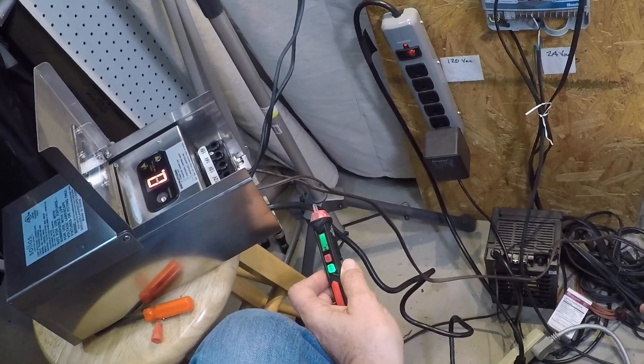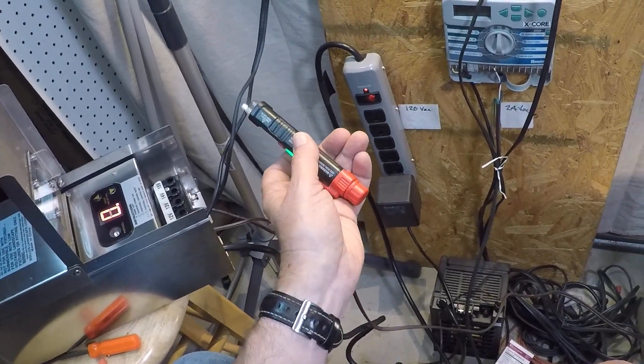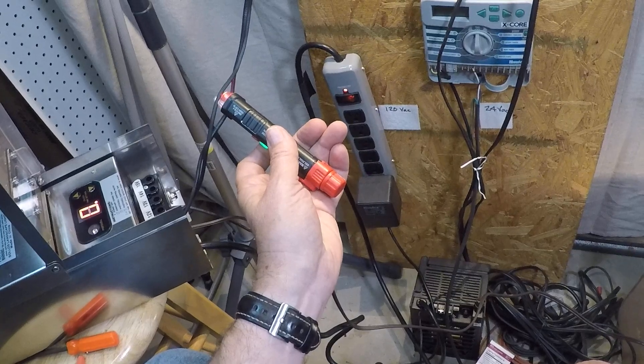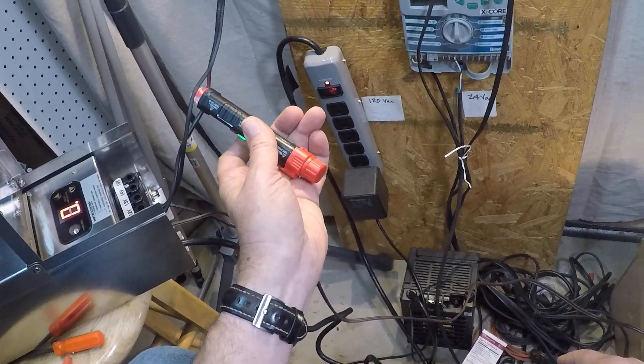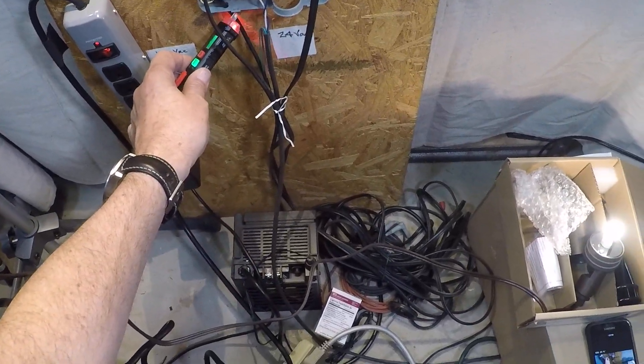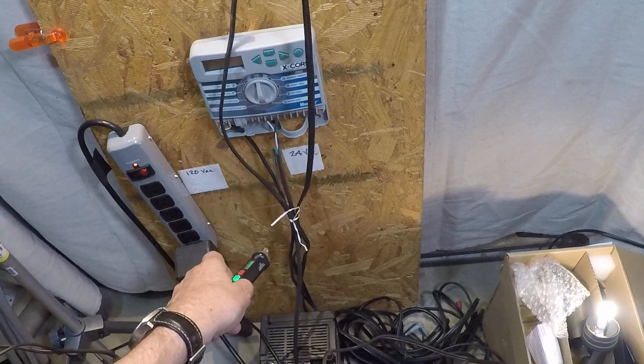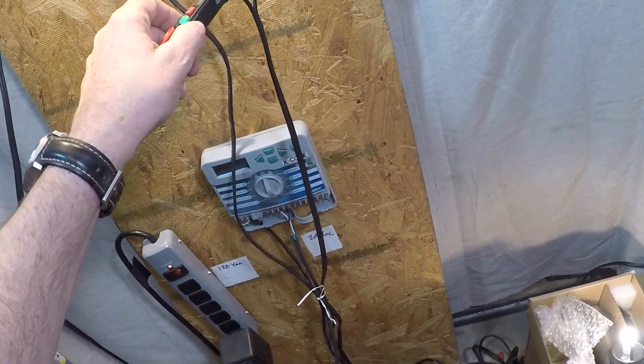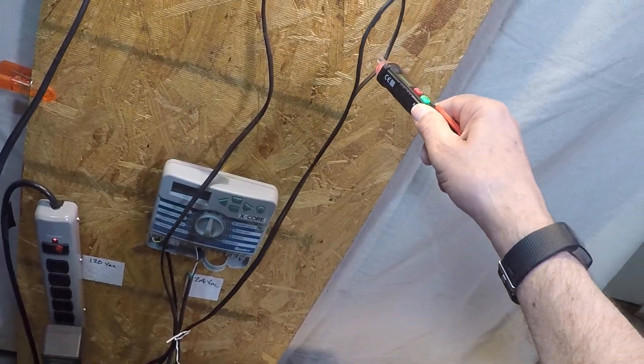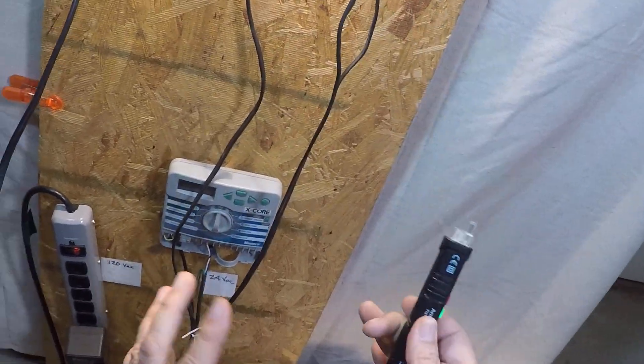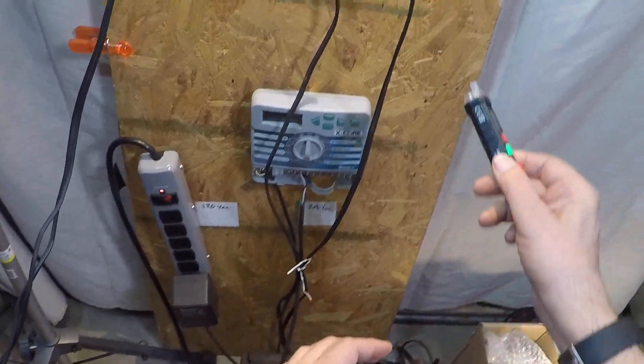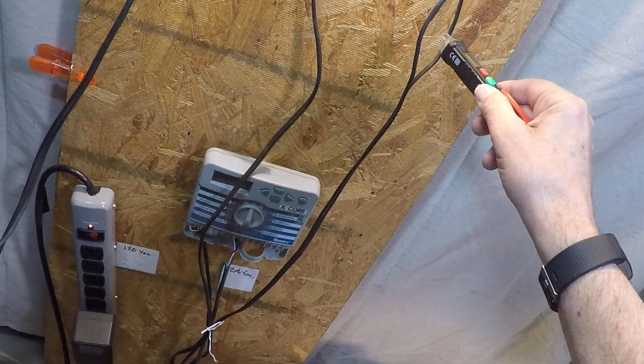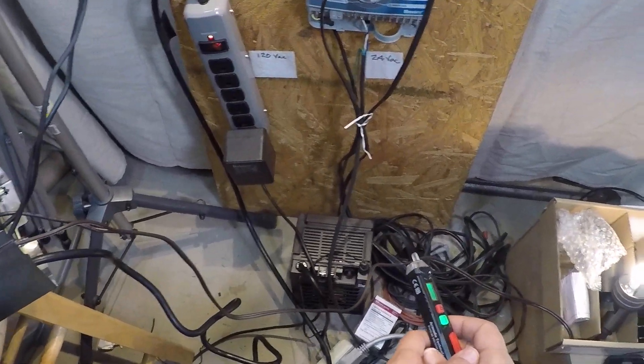When it's in high sensitivity, it still detects 120 but it also detects 12 and 24 volts. You have to be a little bit patient, move it around, let it lay against the wire for a moment just to be sure you're getting the indication. Here's 24 volts going to the controller. Here's a cable with lighting voltage. Sometimes it gives you a spurious indication, just kind of kicks off, makes a beep or something, but be patient. Lay it against the wire, move it up and down the wire a little bit, and you'll become pretty confident that the thing is working correctly.